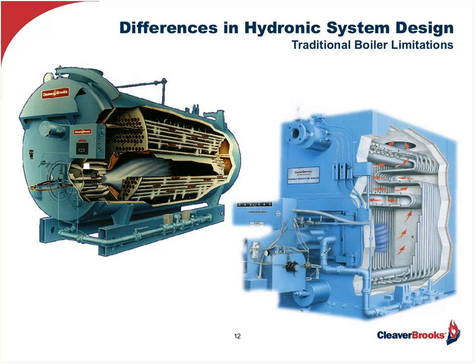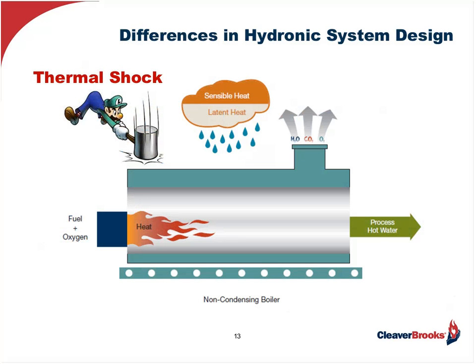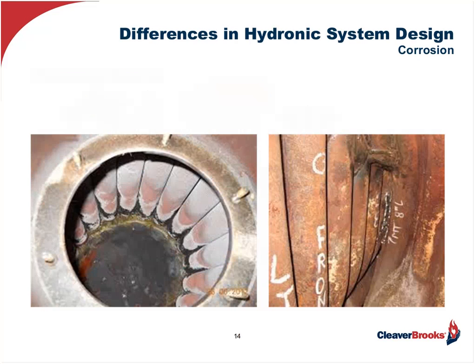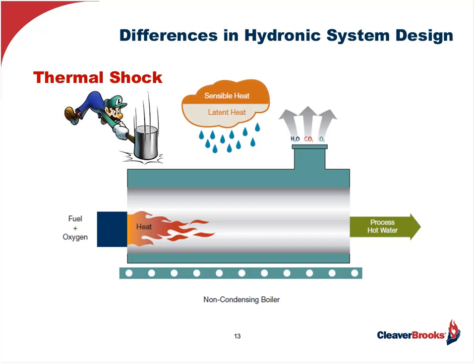So if we look at the history of hydronic systems, remember they came from steam systems originally. And in the 60s, when people started using hydronic systems in lieu of steam systems, they had to use boilers that came from the steam industry. Most of them are either fire tubes or flexible water tubes. They're very robust when used in the manufacturing of steam, but they have some idiosyncrasies that don't make them as good for hydronic systems, especially high-performance hydronic systems. Fire tube boilers especially are subject to thermal shock. They cannot take a high delta T. If the delta T is too high, the tubes will expand and contract, and that's what thermal shock is. They also cannot take water that's too cold for the same reason. Flexible water tubes can take thermal shock. As you saw in the picture, the bent tubes allow for some flexibility as that cold water comes in. But what they can't do is take a cold return temperature.